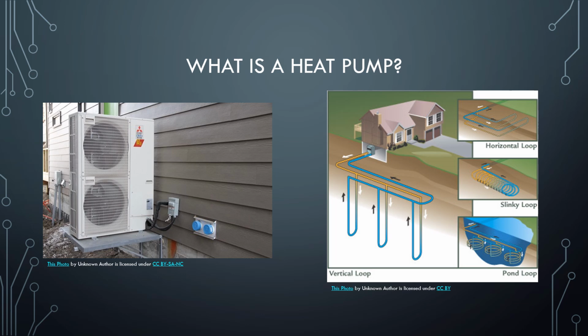In the winter, it can extract heat from the outside air or ground and move it inside. And in the summer, it extracts heat from inside air and moves it outside or into the ground. There are two common types of heat pumps used for space heating. Air source, shown on the left, which extract heat from the air, and ground source, shown on the right, also commonly referred to as geothermal heating, which extract heat from the ground. Heat pumps can also use a body of water, such as a lake or pond, instead of the outside air or ground.